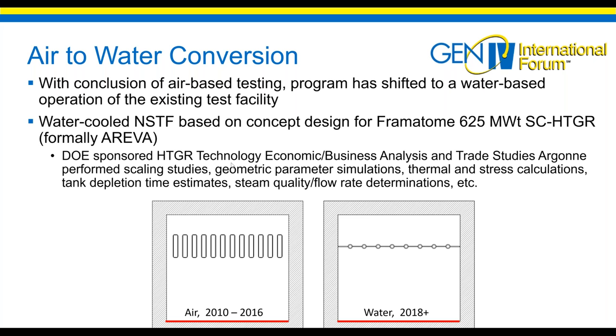DOE sponsored us to look at this, do trade studies, thermal analysis, and calculations to design the system for converting from the air-based system I'm showing in vertical or horizontal cross-section, over to a water-based system, where water-cooled pipes are stitched together by steel plating, and the reactor vessel would radiate and convect to this system. By conduction, heat transfers into the water, which rises through the system, and the reactor cavity wall, or the reactor silo wall behind it, would be kept at a low temperature by virtue of this. This is a system commonly used in high temperature carbon plants in the U.S., both coal and natural gas, but the idea here was to apply it to a nuclear system to qualify it for that type of configuration.